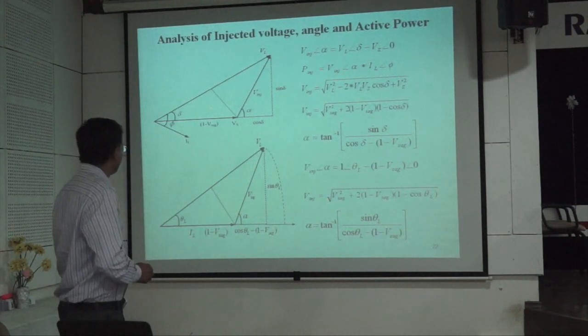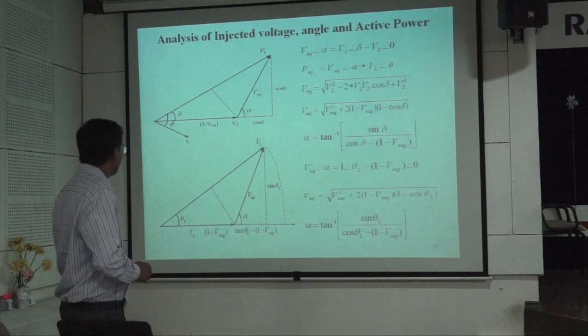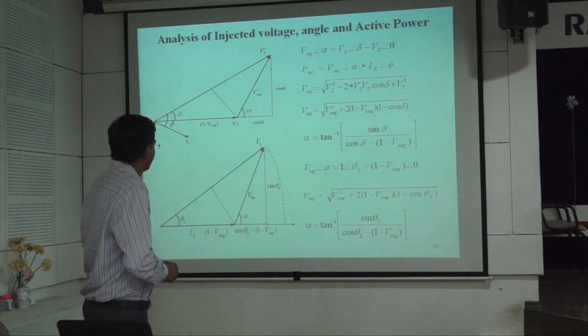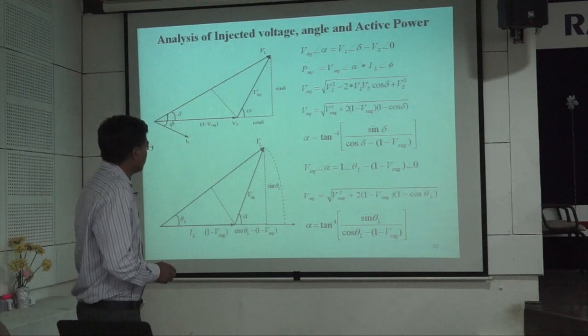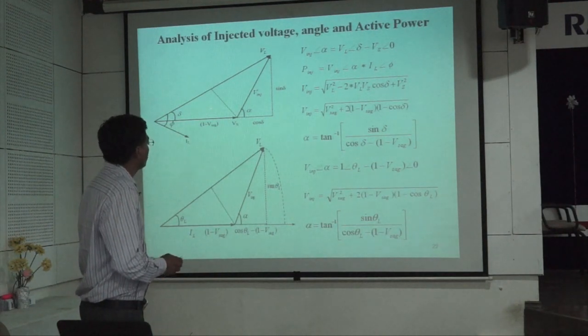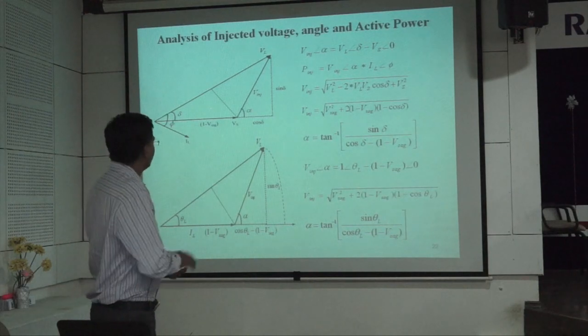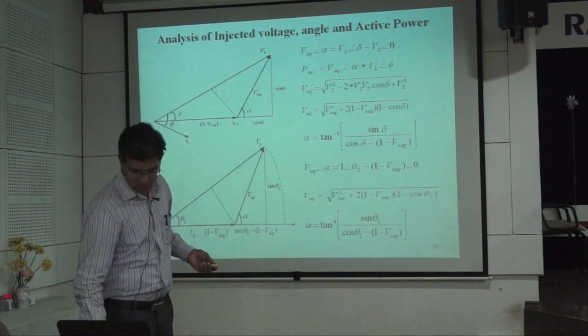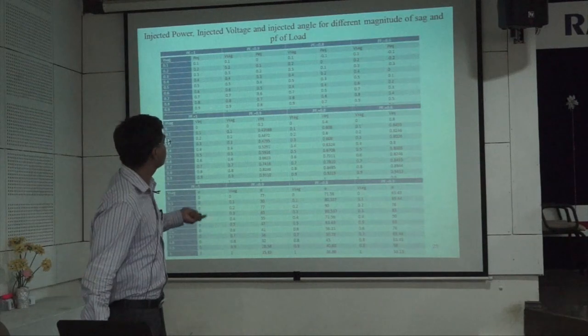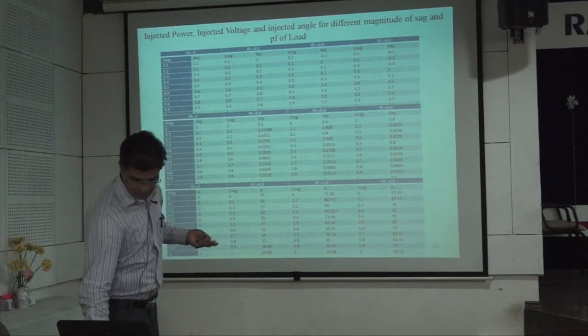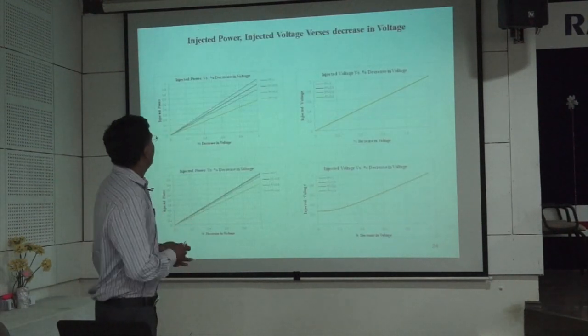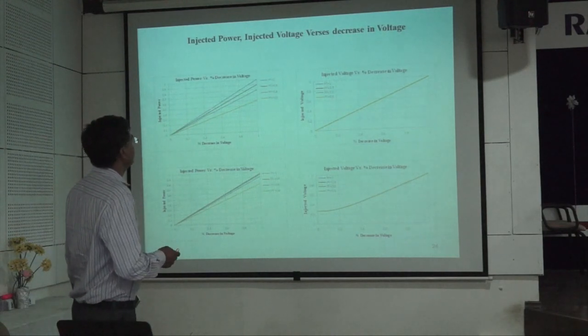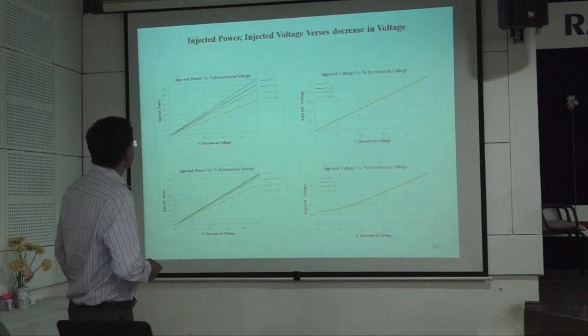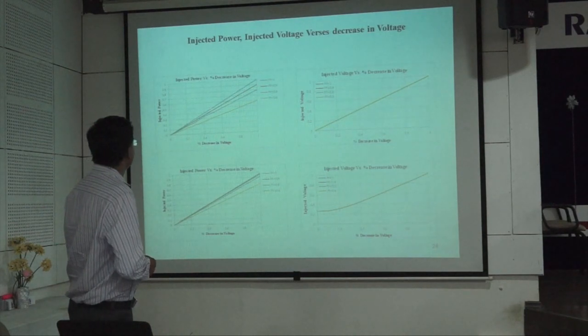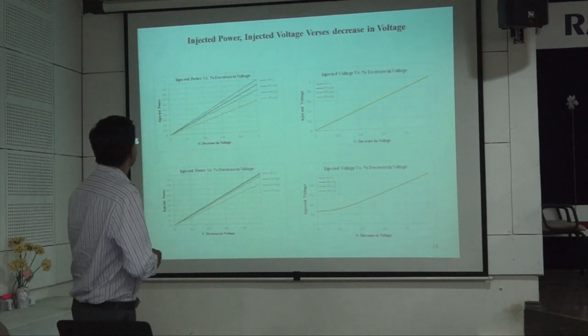This is the case where theta L, the phase jump, is equal to the power factor angle of the load. If this is the case, this is the V injected, alpha injected, and the power injected. Power injection will remain the same because the phase jump has no effect on power injection. These are the various data that are found out. And from the injected power and injected voltage, see here, this is the case of decrease in the voltage from 0 to 1, there is injected power.